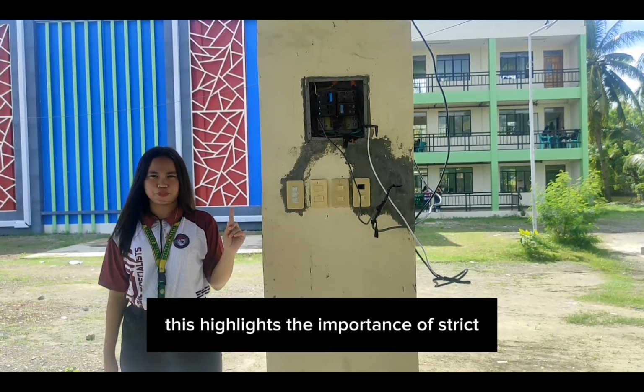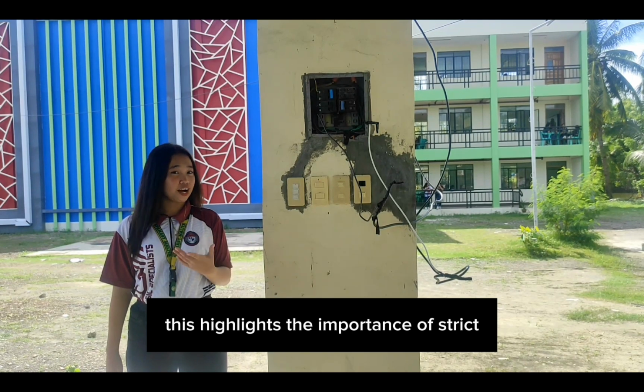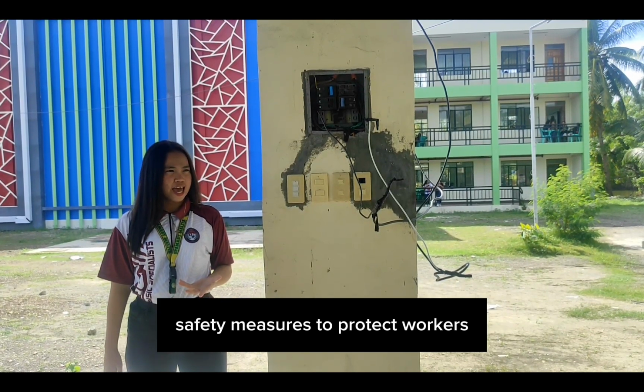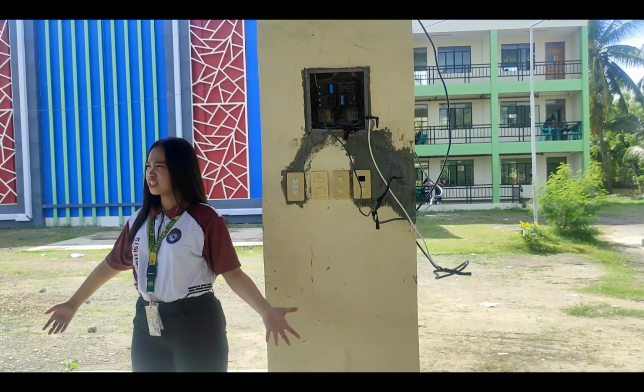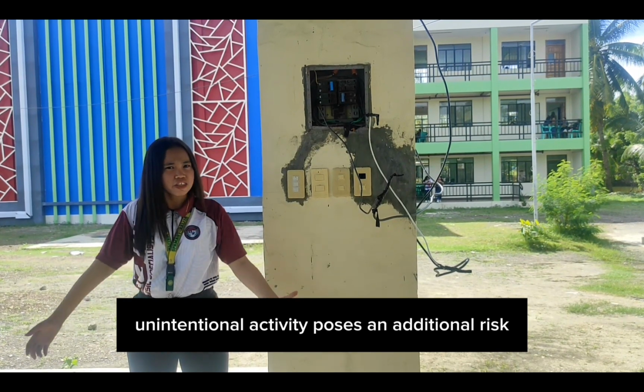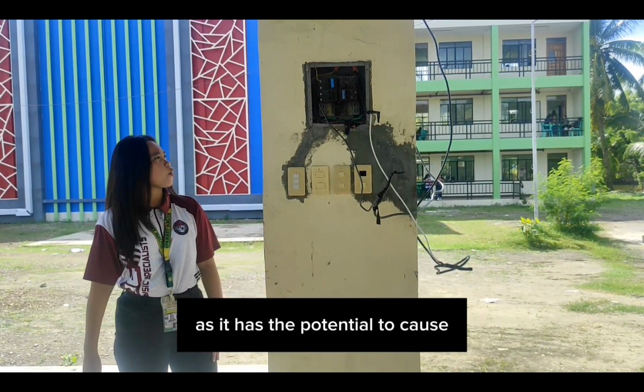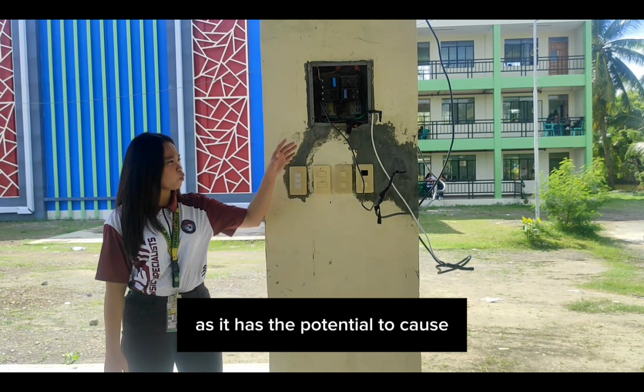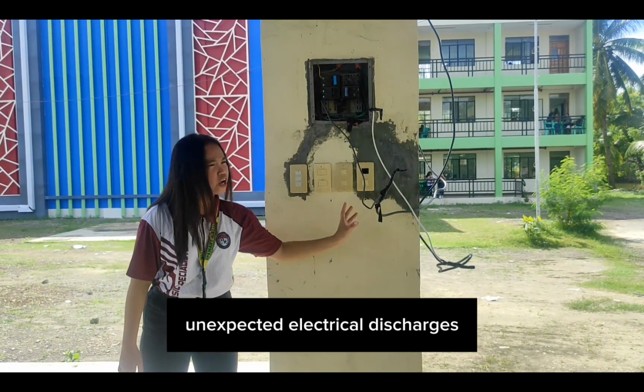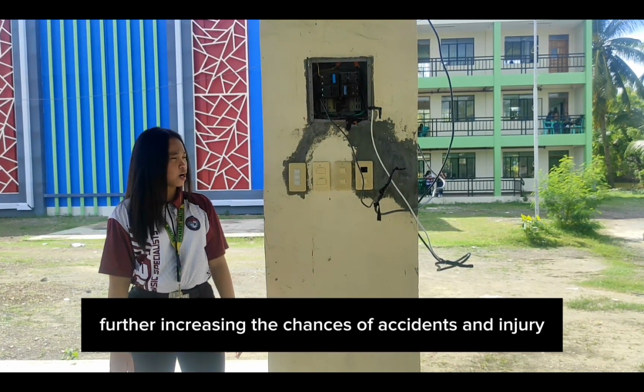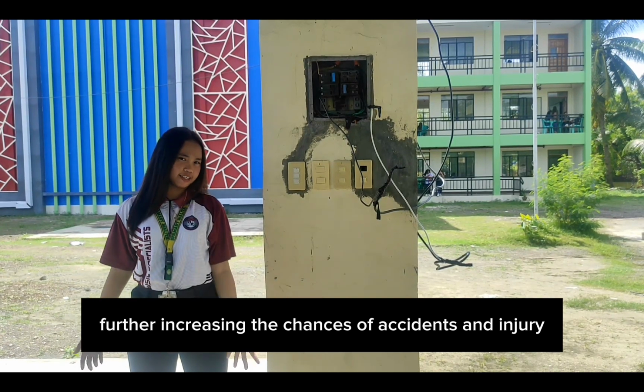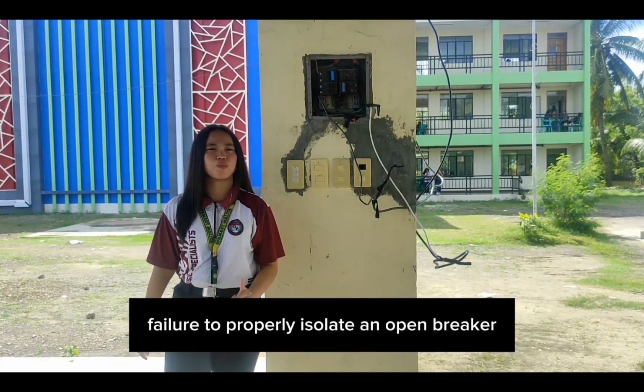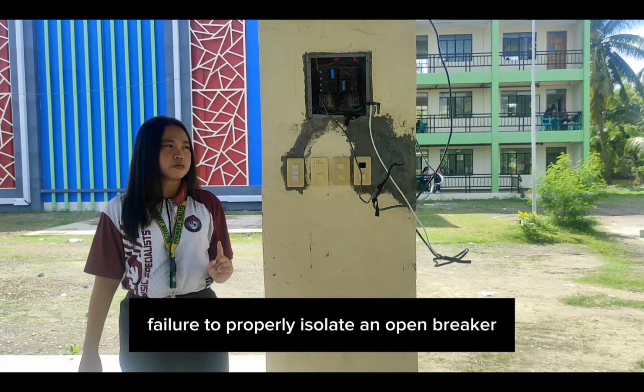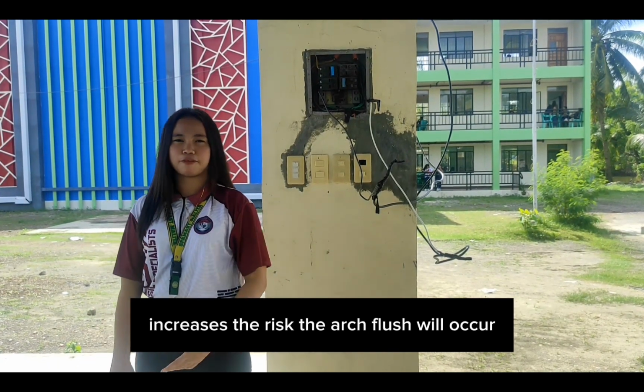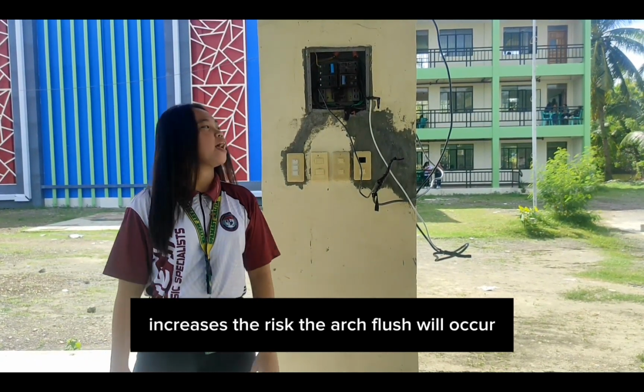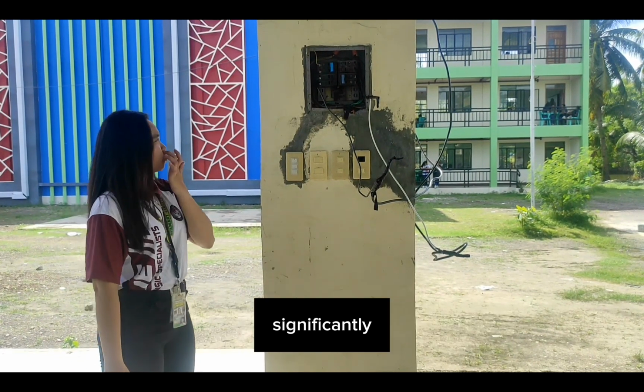This highlights the importance of strict safety measures to protect workers. Unintentional activity poses an additional risk, as it has the potential to cause unexpected electrical discharges, further increasing the chances of accidents and injury. Failure to properly isolate an open breaker significantly increases the risk that arc flash will occur.